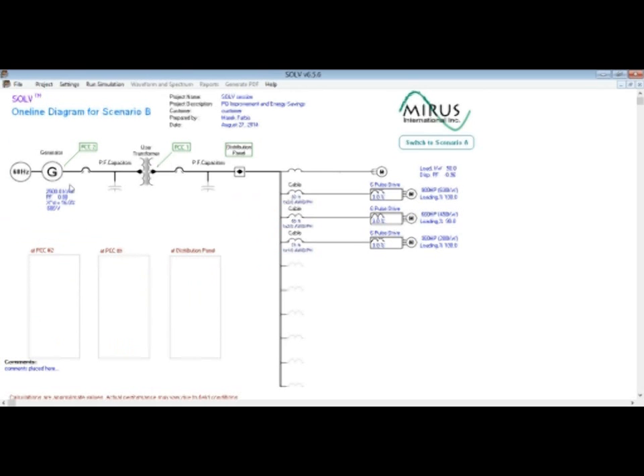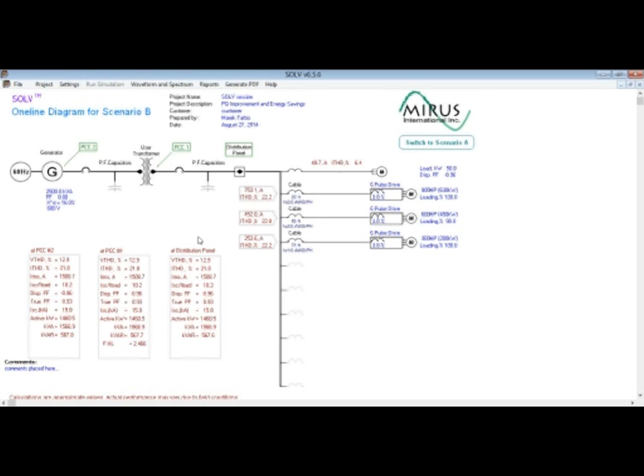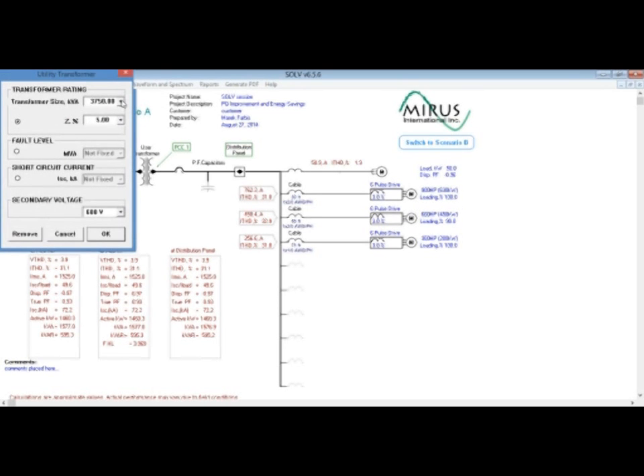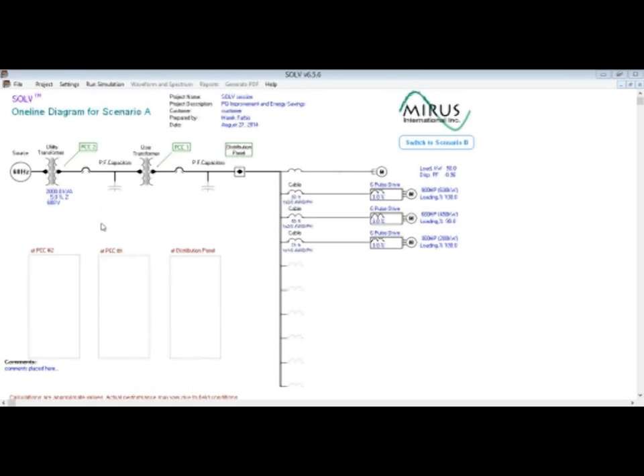So I click OK and run the simulation, and we can see that the current distortion with generator supply is lower, slightly above 22%. However, the voltage distortion in the system is exceeding 12%. Note that the short circuit to load ratio in this case is just about 10, which is almost 5 times lower than with the utility supply. So now to continue our analysis, I will go back to scenario A and change the utility transformer size to a smaller one, let's say 2000 kVA, and I leave the same relative impedance, 5%, and let's run the simulation.